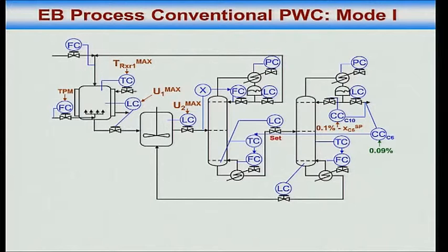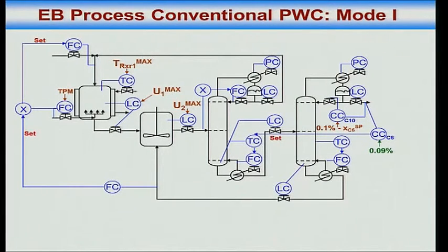Obviously you'd like to keep these at max because that's optimum. Yes or no? What are your 4 unconstrained degrees of freedom? Those are shown, I think, in green. Let's see. You maintain total benzene in ratio with the ethylene, and because you can get snowballing in the DEB recycle loop, what Luyben has suggested is that you maintain the flow of the DEB recycle by adjusting the ratio set point. Okay, this is what has been suggested in that paper by him.